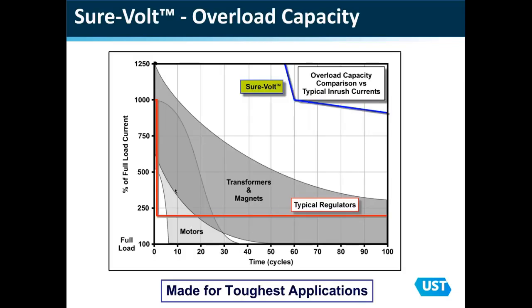This particular product has a very high and robust inrush capacity. Most of the other electronic voltage regulators in our segment have an overload protection of 1000% for 1 cycle. The UST product is 1000% for 1 second, 60 cycles. So a tremendous amount of protection built into the unit to protect it from any potential failures.